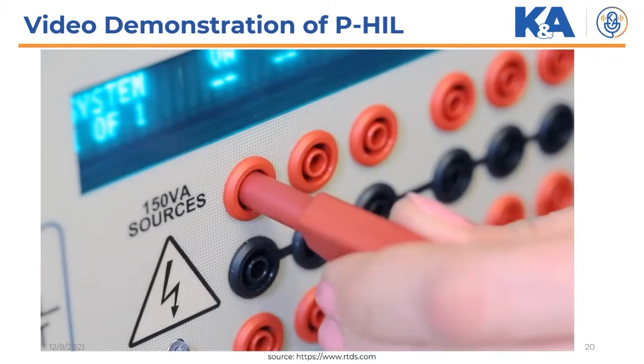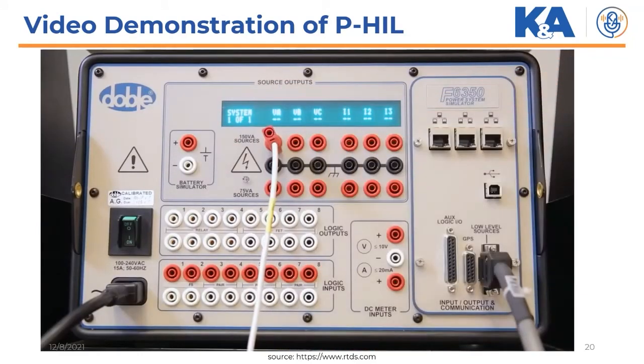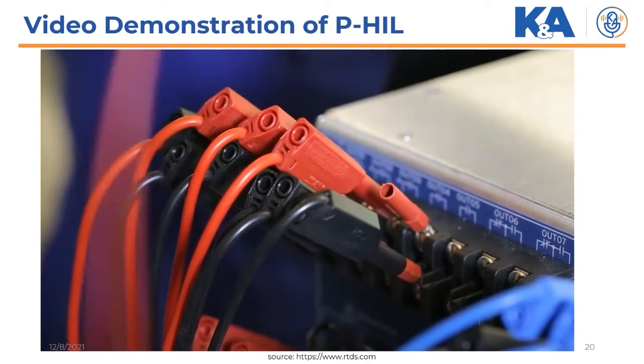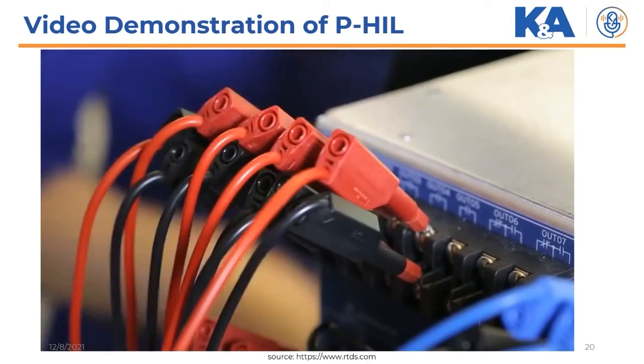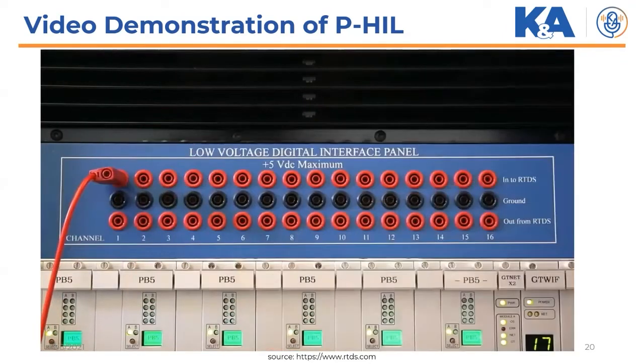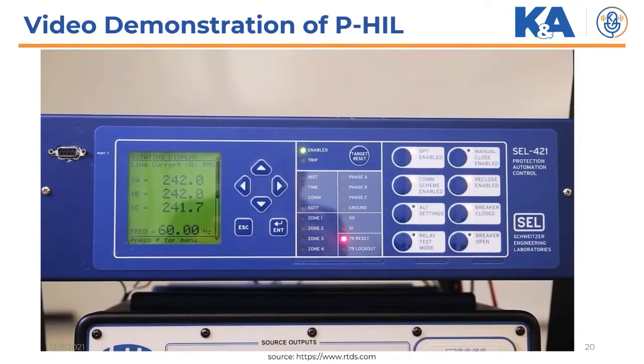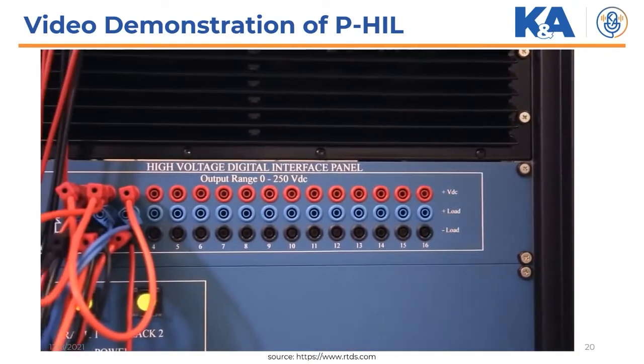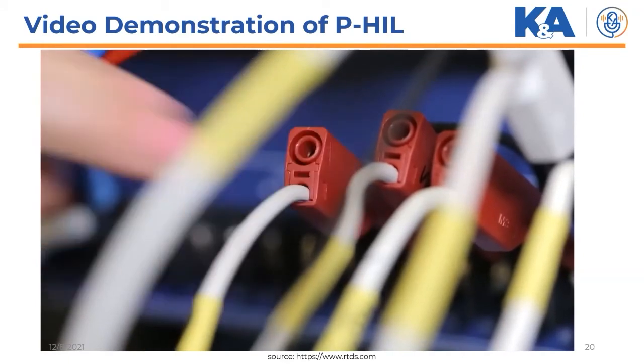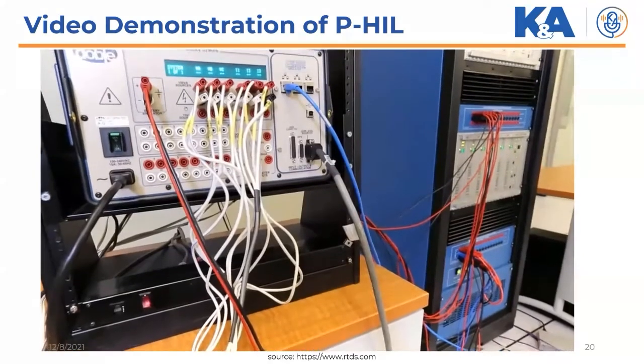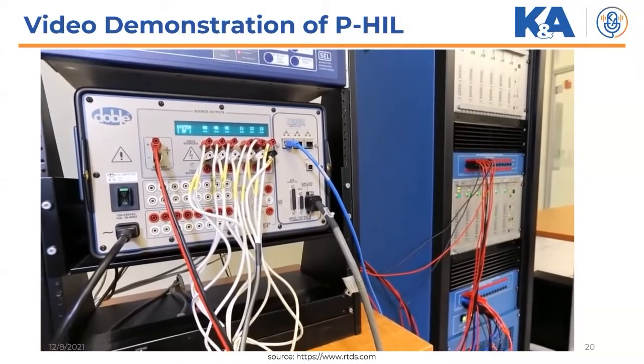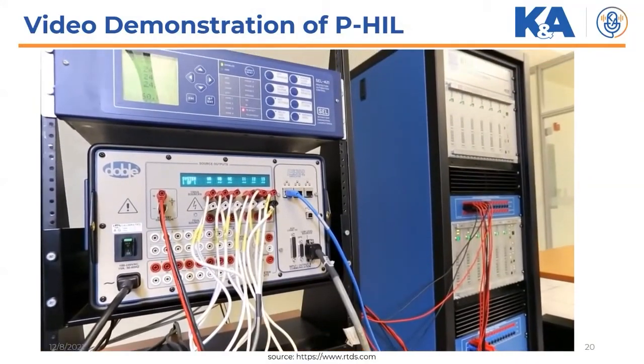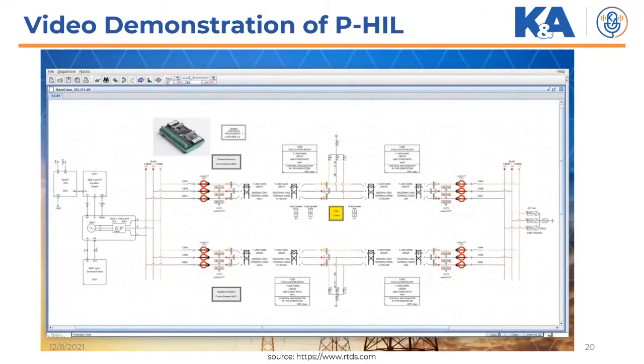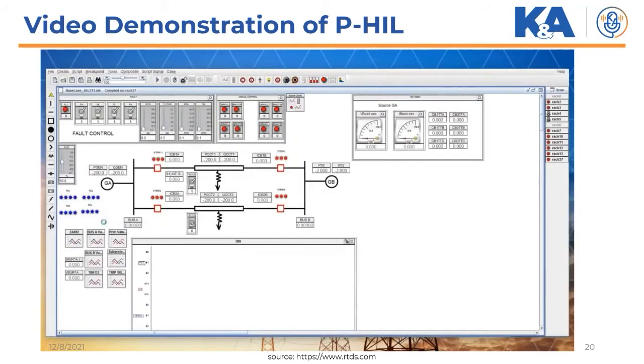The amplifier outputs are then connected to the protective relay's analog inputs. The protective relay's output contacts are connected to the RTDS simulator's digital interface panel to communicate breaker commands. The simulator's high voltage panel is connected to the relay's input channels to communicate breaker status. In this way, we've created a closed loop between the RTDS simulator and the protective relay. Once our hardware is set up and everything is configured properly in our software, we can compile our case and open the runtime console to start our simulation.